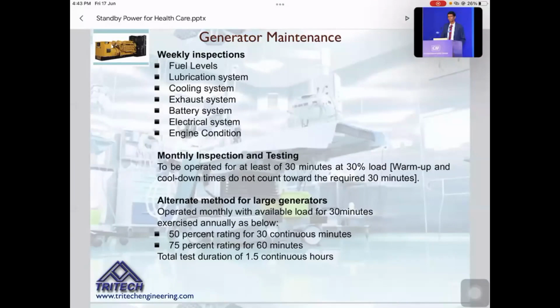So for 30 minutes it should be operated at 30% load, which is to be done monthly. If it's a very large generator, you will not be able to have the 30% load, so you can operate with the available load for 30 minutes. Yearly, 50% for 30 continuous minutes, because you may have to bring in the load from outside, and 75%. So this is the testing norm for generators, apart from the inspection.